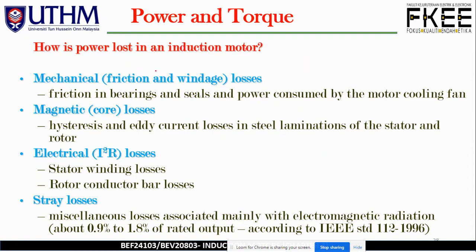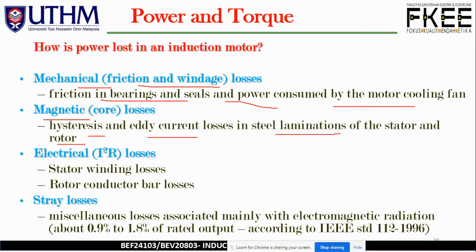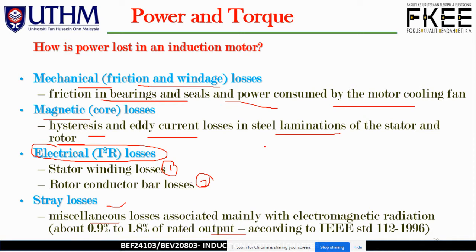To summarize power losses in an induction motor: friction and windage losses occur from the shaft and bearings and power consumed by the motor cooling fan. Magnetic core losses are due to hysteresis and eddy current losses in the steel lamination of the stator and rotor. Electrical I²R losses consist of stator winding losses and rotor conductor bar losses. Finally, stray or miscellaneous losses associated mainly with electromagnetic effects are about 1% to 1.8% of rated output, according to IEEE standard 112-1996.